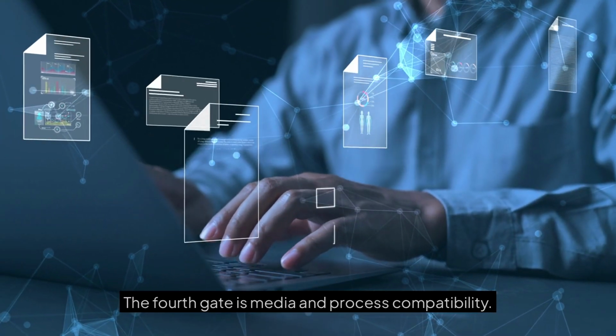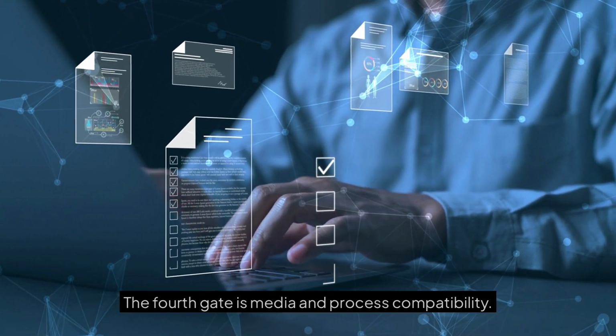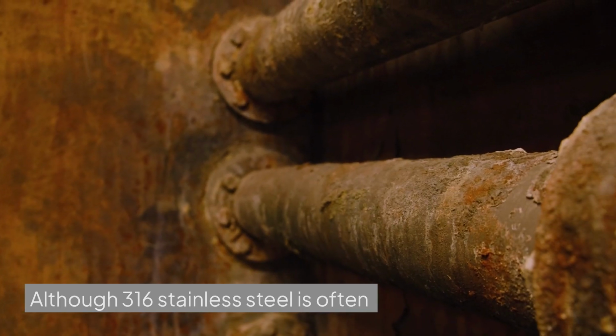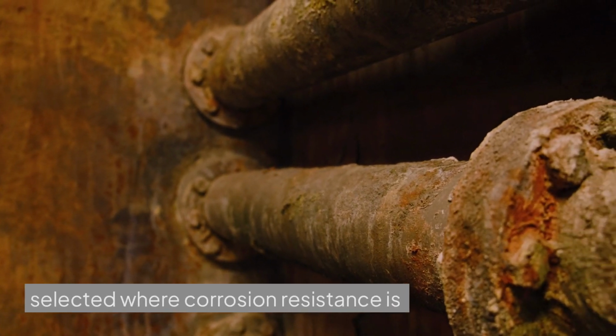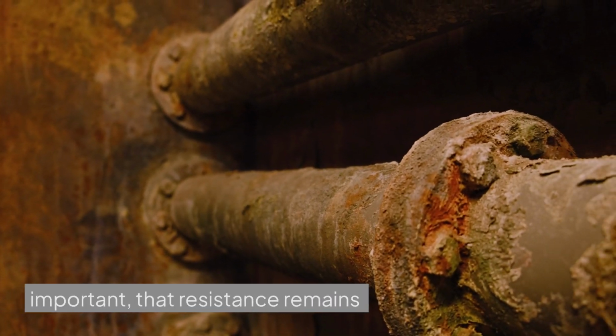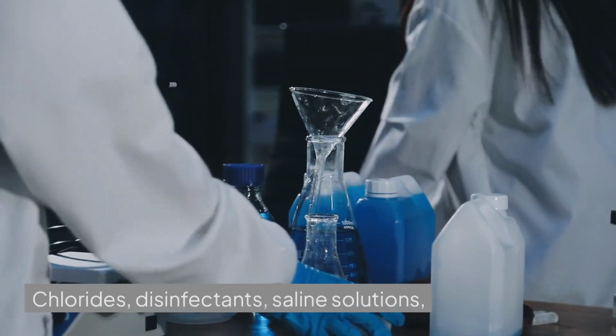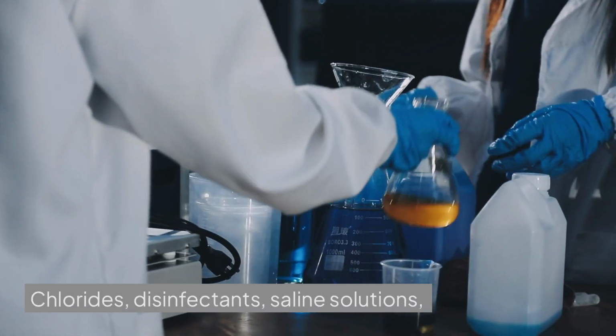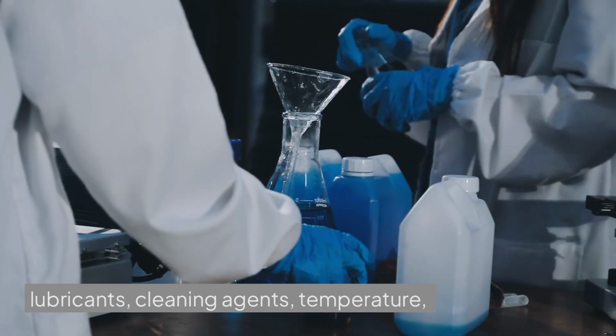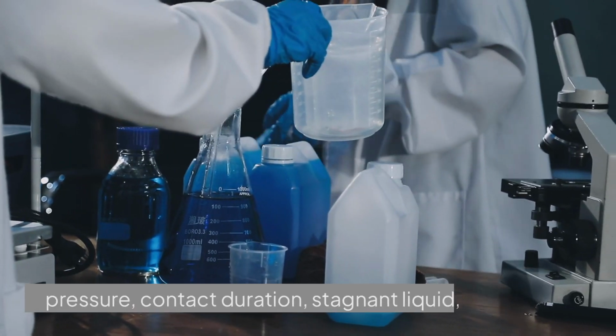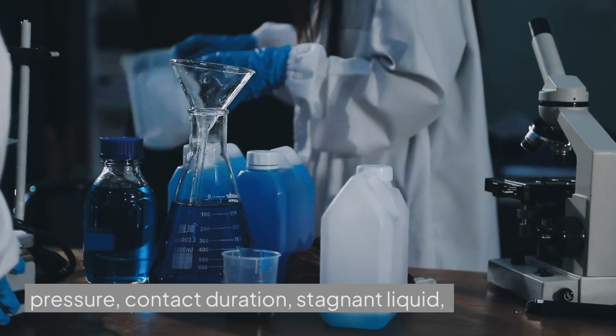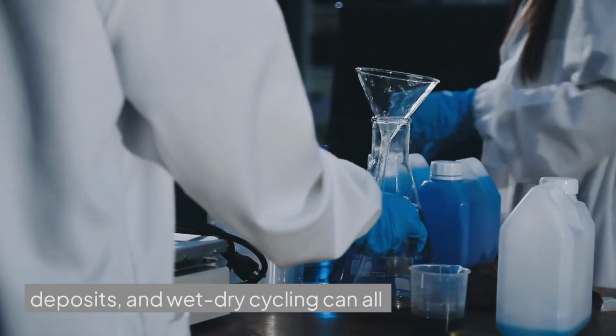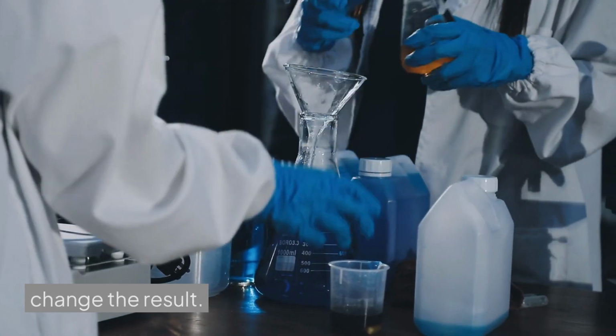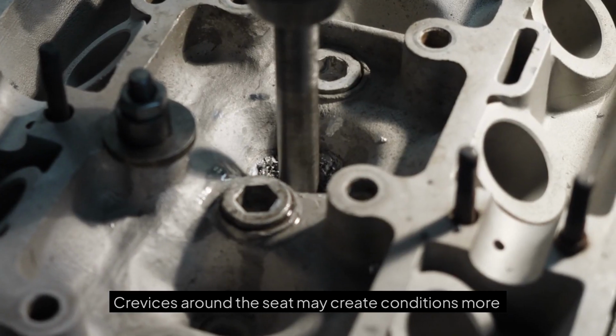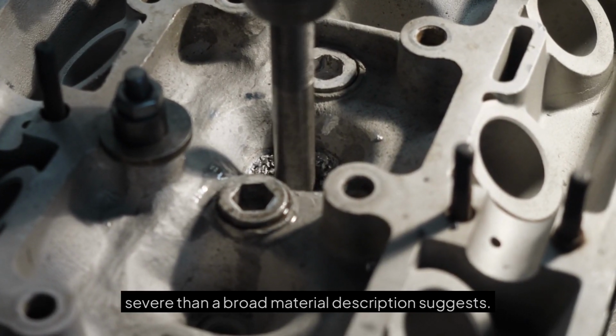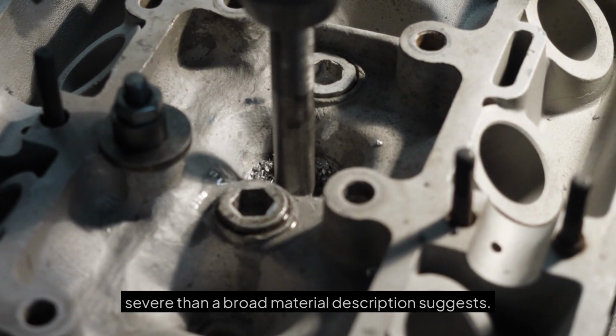The fourth gate is media and process compatibility. Although 316 stainless steel is often selected where corrosion resistance is important, that resistance remains conditional. Chlorides, disinfectants, saline solutions, lubricants, cleaning agents, temperature, pressure, contact duration, stagnant liquid, deposits, and wet-dry cycling can all change the result. Crevices around the seat may create conditions more severe than a broad material description suggests.